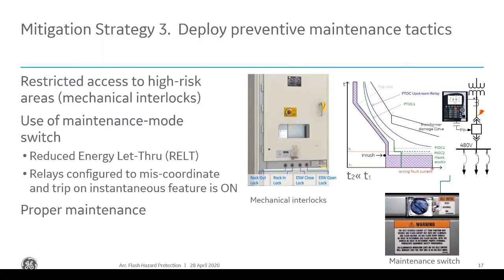The disadvantage is that it's not in service all the time, only when the maintenance switch is in the maintenance position. And obviously you need controls for that. If you want to make sure that switch is on when personnel are in the area, you need to have some engineering controls for that. When it is in the maintenance position, the con is for faults external to the downstream breakers: a fault downstream of the breaker will cause the main breaker to trip. So you risk over-tripping your main breaker for an incident. And if you don't have any sort of backup, then for a fault downstream in one single feeder, you could take out multiple pieces of switchgear and maybe have a blackout in your plant or facility.